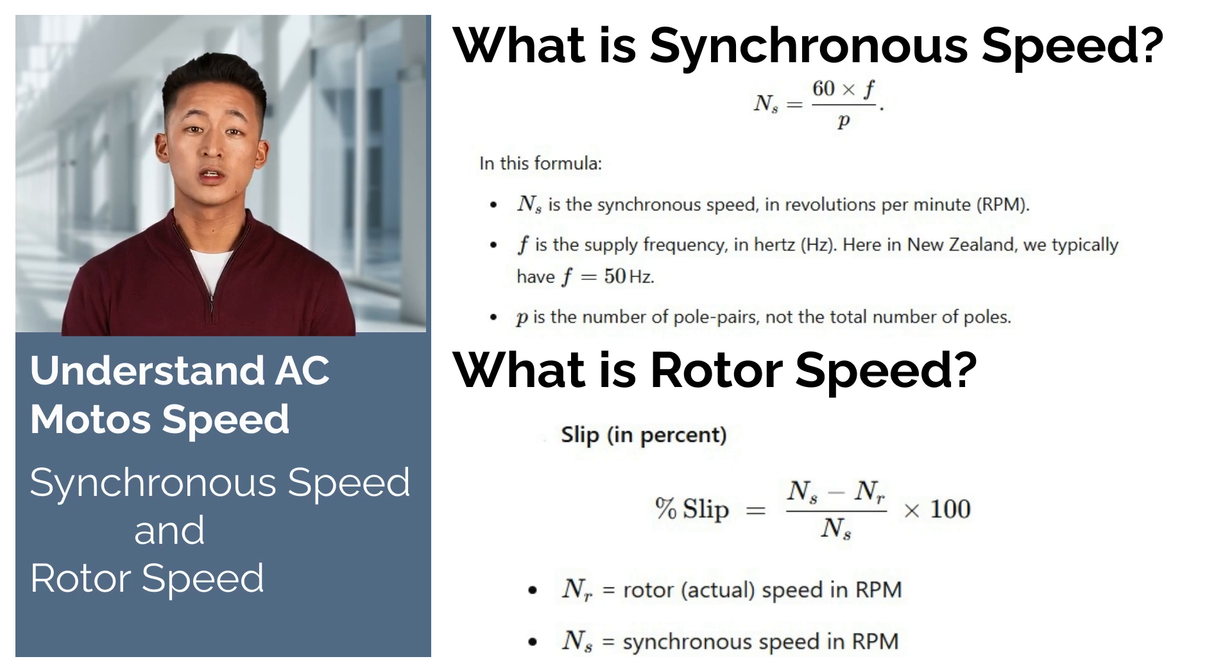The difference in speed between the synchronous speed and rotor speed is called slip. Slip, measured as a percentage, is calculated using this formula: slip percent equals the quantity synchronous speed minus rotor speed, divided by synchronous speed, multiplied by 100.